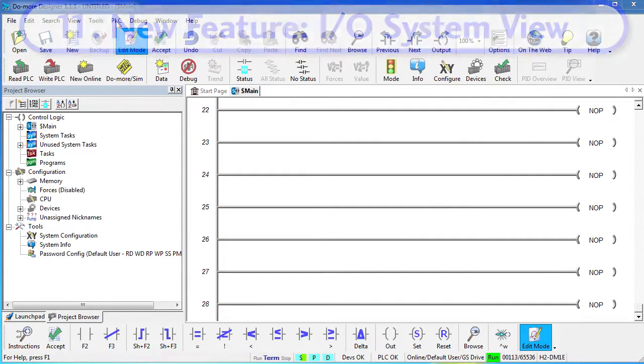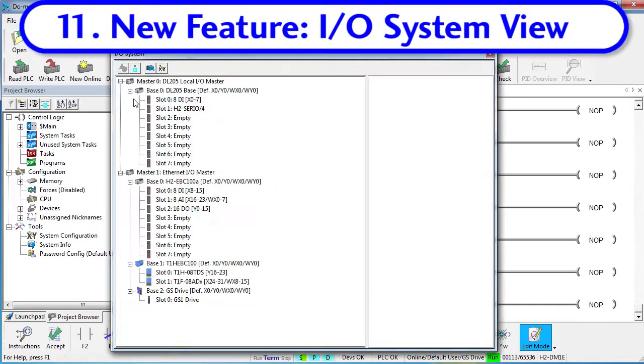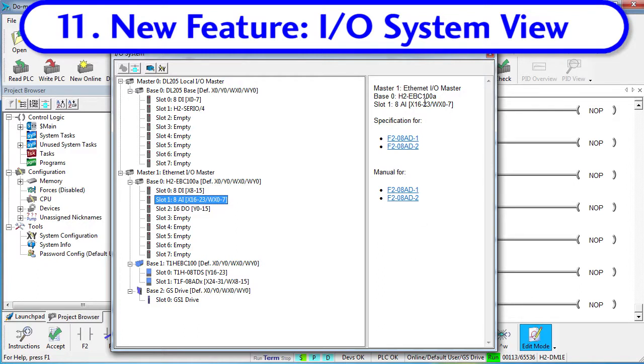The IOSystemView utility, located under the PLC menu, is a new utility that shows your entire system at a glance. Here's my 205 base, my Ethernet I/O master, and all the slaves reporting into that Ethernet port — my EBC100, my Terminator I/O, and my GS drive. If you have an error on any of these modules it will turn red, and over here you can view all the information about that module, the specific error, and even pull up direct links to the specs and manuals for each module in the system. This is all discussed in detail in the Ethernet I/O troubleshooting video.